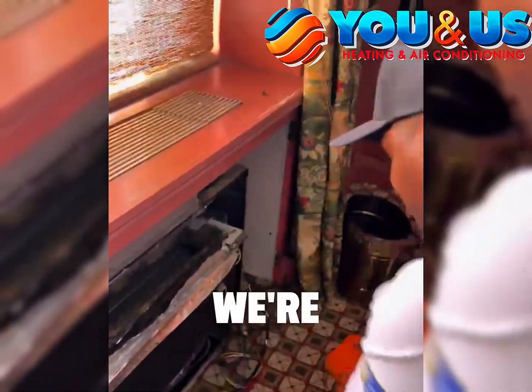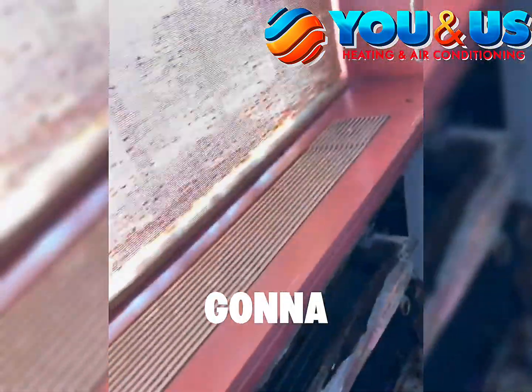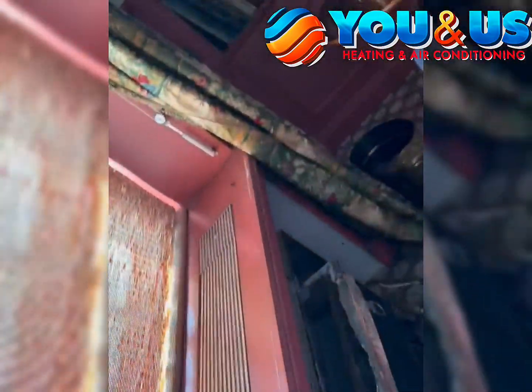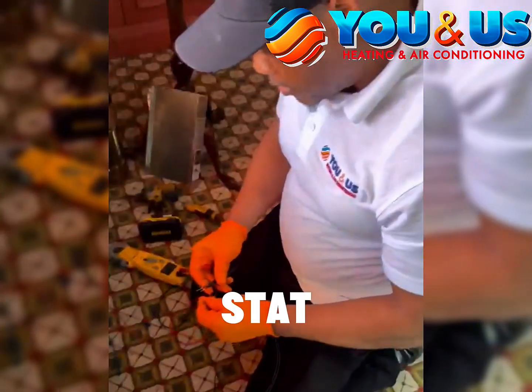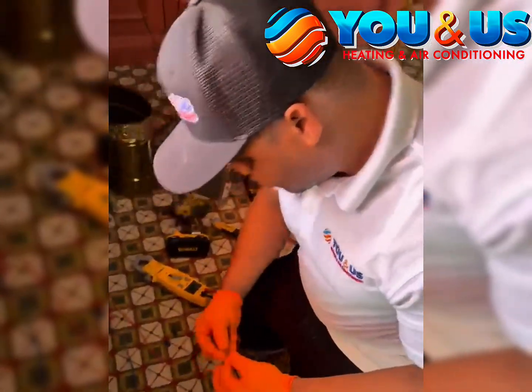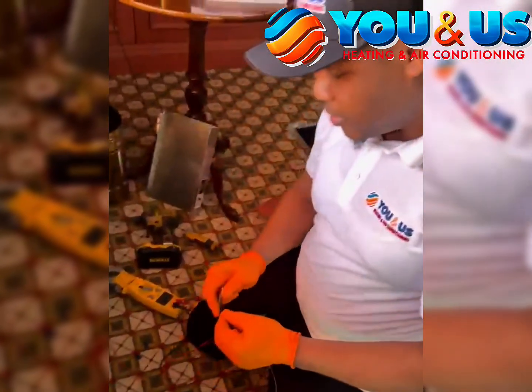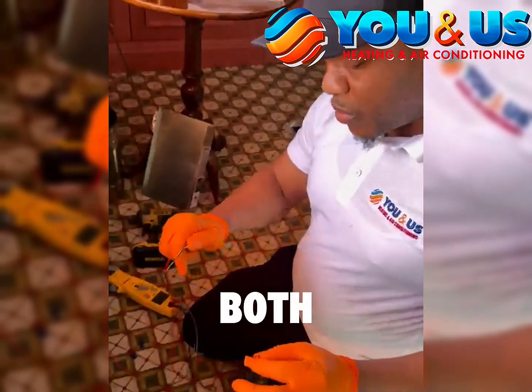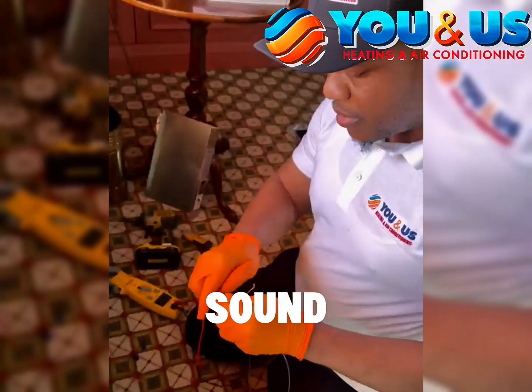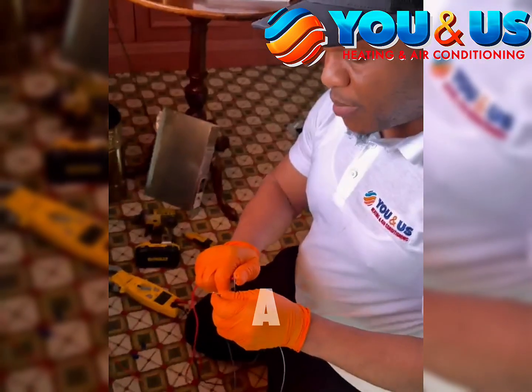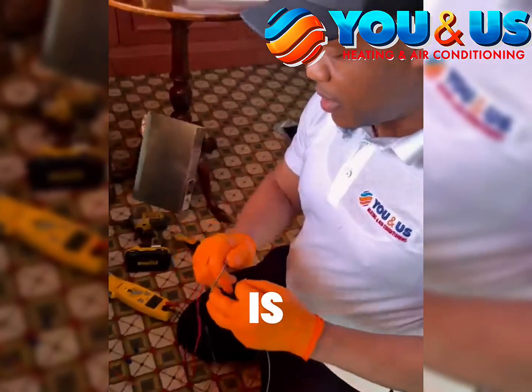So we're gonna do a continuity test on the Aquastat. I'm gonna touch both wires. We're supposed to have a beeping sound like that, but we're not getting a beeping sound. That means the Aquastat is dead.